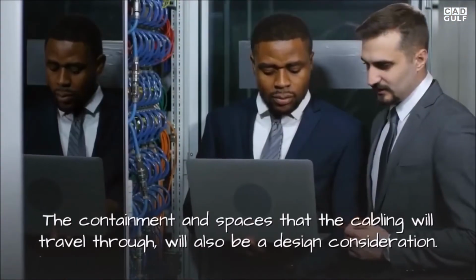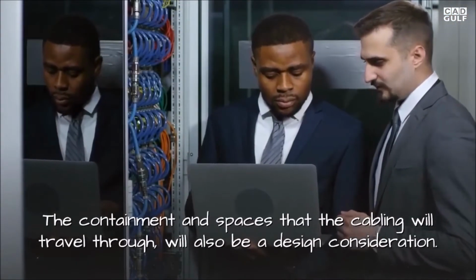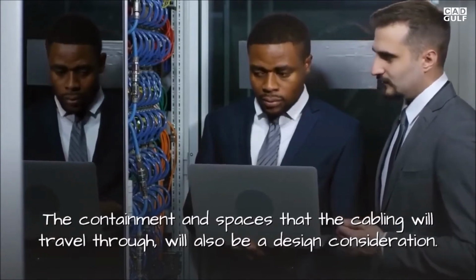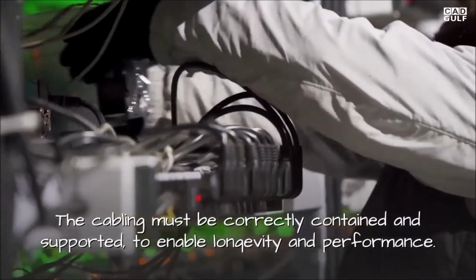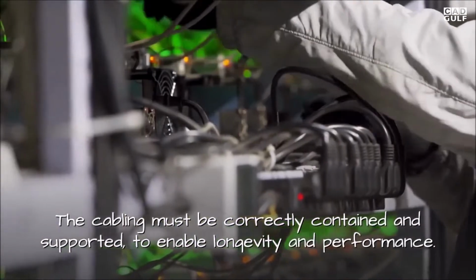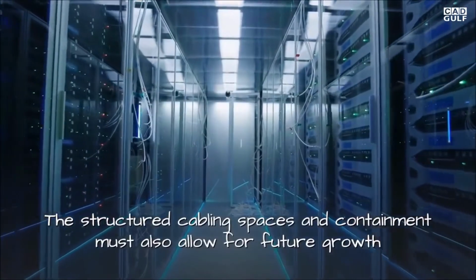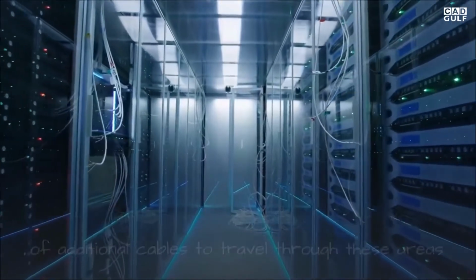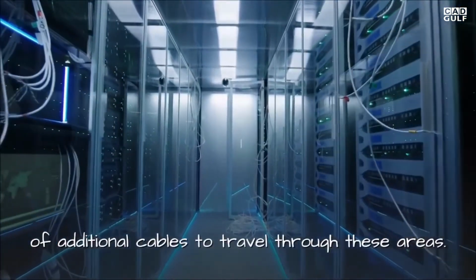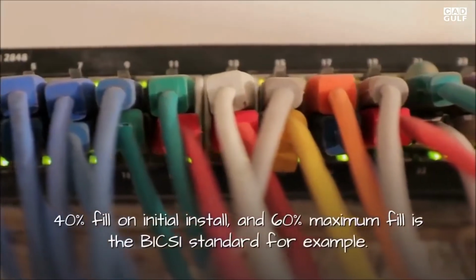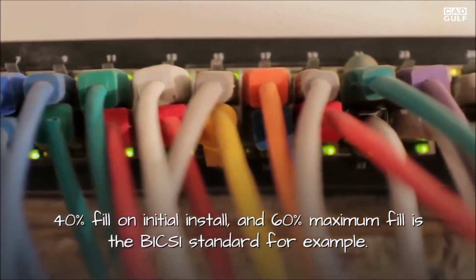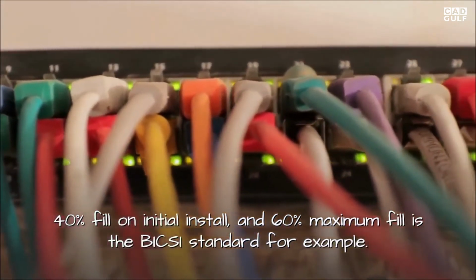The containment and spaces that the cabling will travel through will also be a design consideration. The cabling must be correctly contained and supported to enable longevity and performance. The structured cabling spaces and containment must also allow for future growth of additional cables to travel through these areas. 40% fill on initial install, and 60% maximum fill is the BICSI standard.